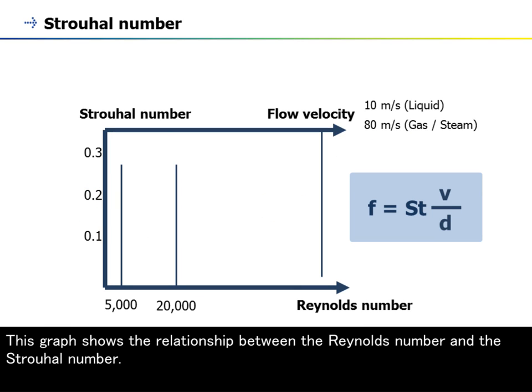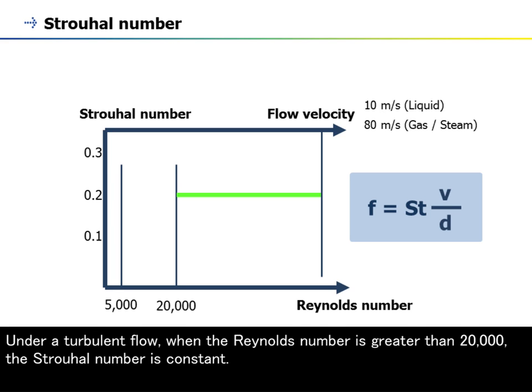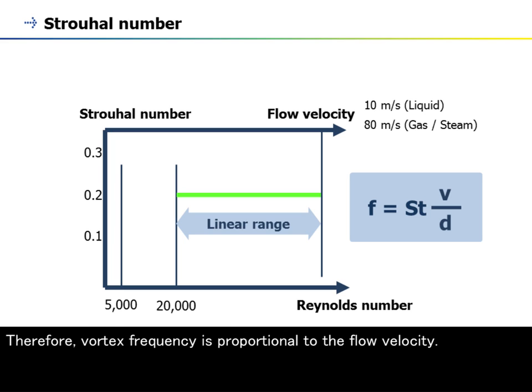This graph shows the relationship between the Reynolds number and the Strouhal number. Under a turbulent flow, when the Reynolds number is greater than 20,000, the Strouhal number is constant. Therefore, vortex frequency is proportional to the flow velocity.